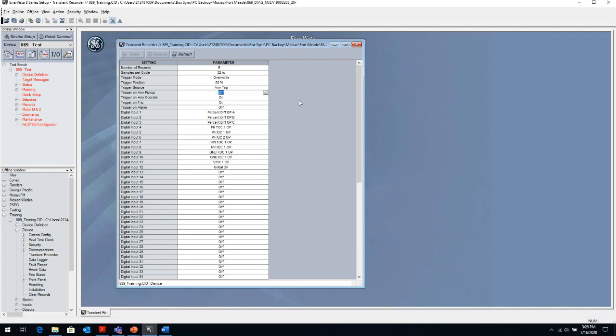Pickup is basically if you have a time overcurrent element, you have a fault, the time overcurrent element picks up, it hasn't timed out yet, it's waiting to be timed out. So you can have a record created when it picks up and a record created when it trips, because the time between pickup and trip could be a long time depending on your TOC time dial setting. Then the other things are digital inputs.